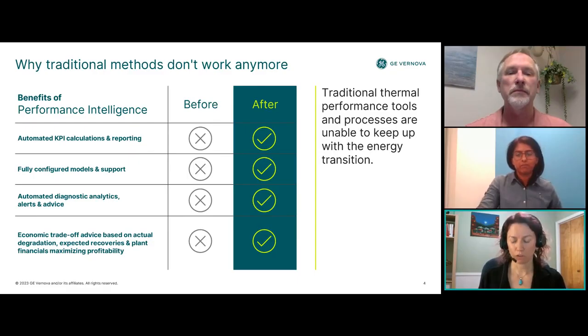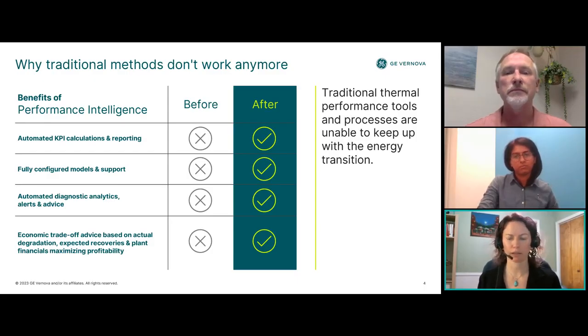We had a customer who was operating at part load through the shoulder season. They worked with us on that modeling and detected multiple issues, opportunities for efficiency improvements, that they were able to address before peak season and before being called to full load, where they would have had a 10 megawatt shortfall. Really significant. The factors were compressor fouling, combustion tuning, things common in thermal performance, but that they wouldn't have had visibility into without the software tool.